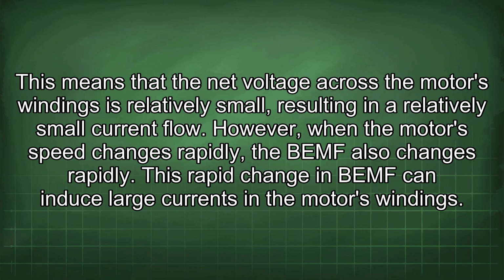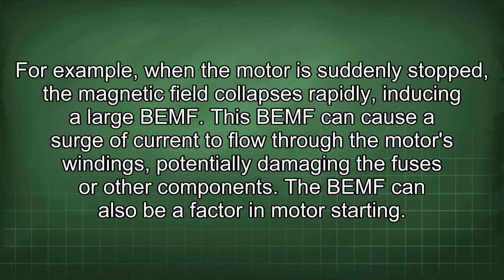However, when the motor's speed changes rapidly, the BEMF also changes rapidly. This rapid change in BEMF can induce large currents in the motor's windings. For example, when the motor is suddenly stopped, the magnetic field collapses rapidly, inducing a large BEMF. This BEMF can cause a surge of current to flow through the motor's windings, potentially damaging the fuses or other components. The BEMF can also be a factor in motor starting.